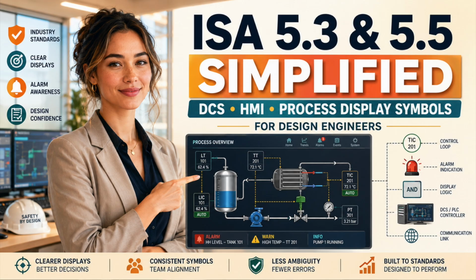The most valuable early decision is to build representative displays before mass production. Create an overview, a process area display, a rotating equipment display, a control loop display, a sequence display, a package interface, and a failure scenario. Put operators in front of them. Ask them to trace flows, find alarms, identify bad data, locate failed permissives, and transfer control. Watch where they hesitate. Hesitation is design information. A process graphic can look excellent in a presentation and still fail in a control room.